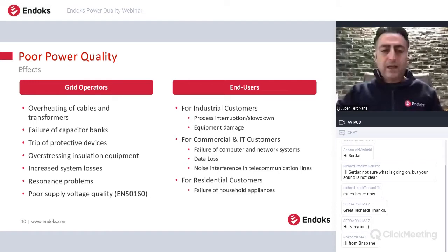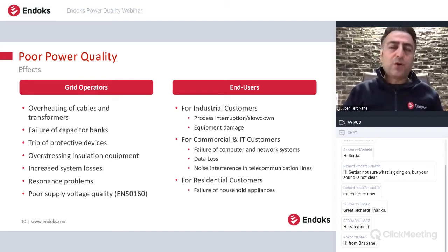And what are the effects of poor power quality? There are, of course, two stakeholders here: the grid operators and the end users. For the grid operators, power quality problems cause overheating of cables or transformers because of harmonics and reactive power flow, failure of capacitor banks, mostly because of harmonics, and the malfunctioning and tripping of protection devices, again because of notches or harmonics.